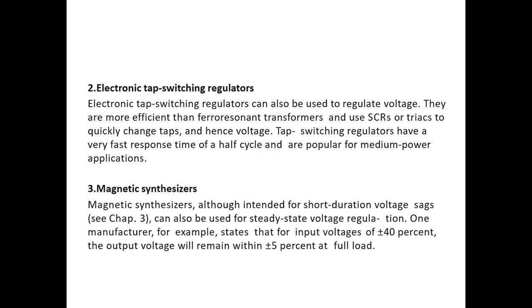Now, electronic tap switching regulators. Electronic tap switching regulators can also be used to regulate voltage. They are more efficient than ferroresonant transformers and use SCRs or triacs to quickly change the taps, and hence the voltage. Tap switching regulators have a very fast response time of a half cycle and are popular for medium power applications. This is the perfect example of an OLTC, that is, an on load tap changer.